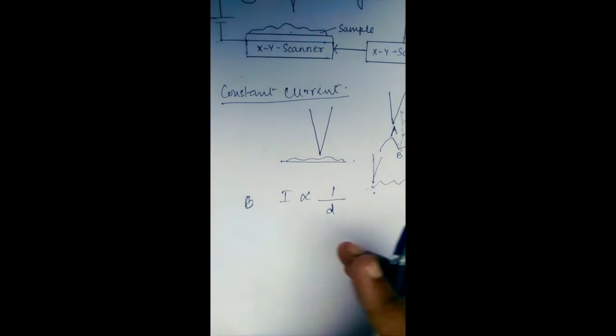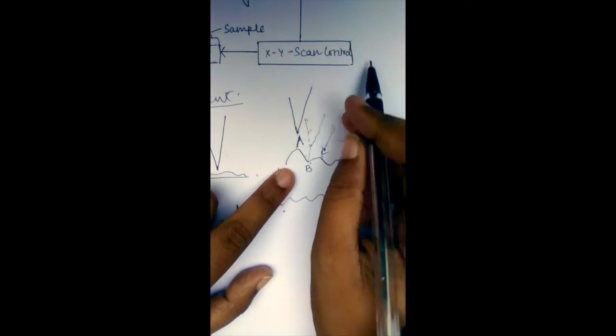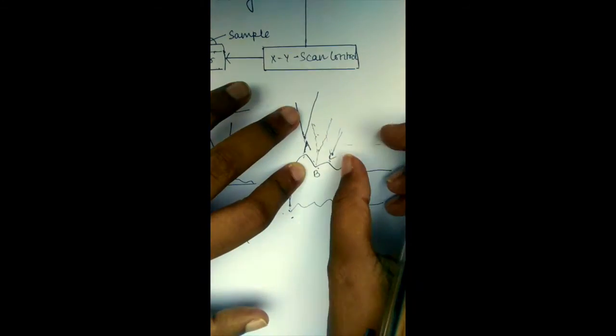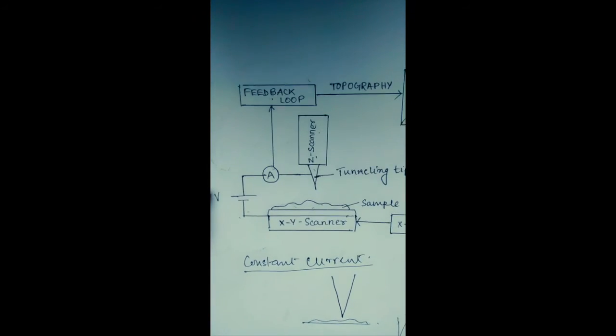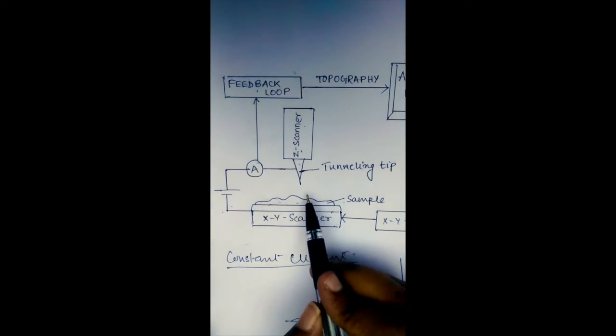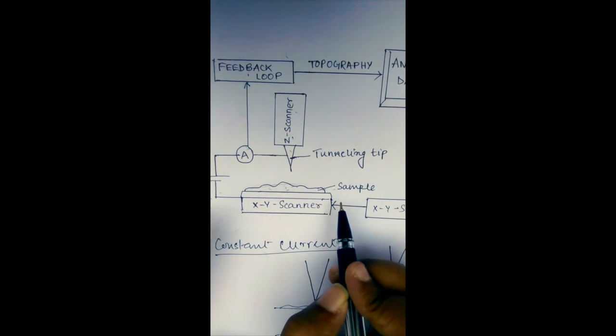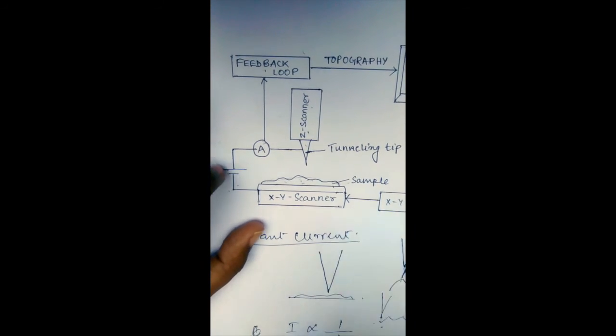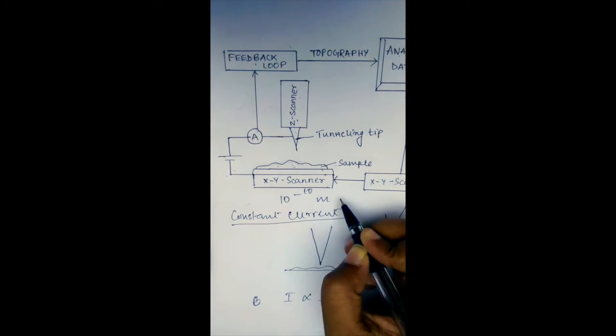In the constant current mode, the current is kept constant while the tunneling tip moves up and down across the surface, and its motion is scanned and sent to the feedback loop. Regarding sample requirements, since the electron is tunneling through the sample to the tip, the surface must be conducting. Biological samples usually cannot be used in a scanning tunneling microscope, but for physics and chemistry purposes it can measure dimensions up to 10 to the power of minus 10 meters, which is one Angstrom.